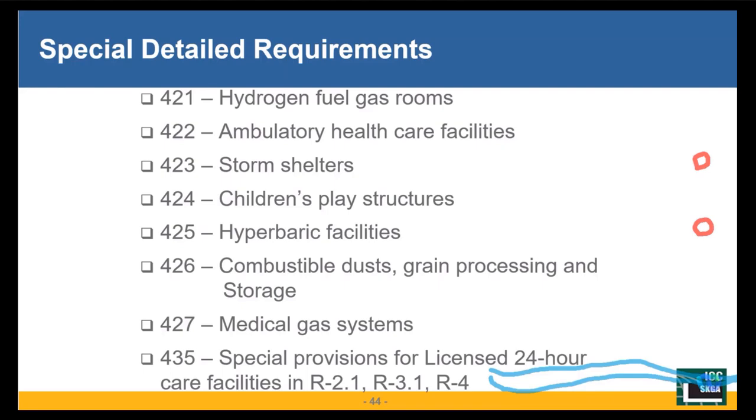Med gas systems, or any gas systems used for healthcare related facilities to help patients or for veterinary care, must comply with special requirements, subsections within 427 and the fire code. There are requirements for storage containers where they're stored, and the quantities cannot be permitted more than certain amounts, and otherwise they have to be located in a 1 hour exterior room or 1 hour interior room or gas cabinets constructed as specified in the code.